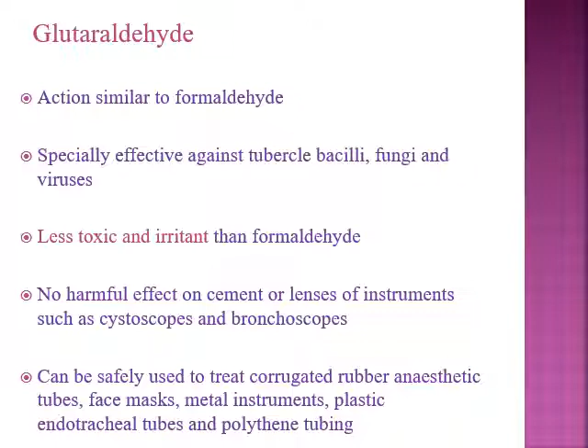Then glutaraldehyde, whose action is similar to formaldehyde. It has a specific effect against tubercle bacilli, fungi, and viruses. It is less toxic and irritant than formaldehyde, with no harmful effect on the cement or lenses of instruments such as cystoscopes or bronchoscopes. It can be safely used to treat corrugated rubber anesthetic tubes, face masks, metal instruments, plastic endotracheal tubes, and polythene tubing. Glutaraldehyde comes in two forms, alkaline and acidic. The alkaline 2% solution requires 10 hours of contact time. It is available as Cidex and 3M germicides. Then the acidic form was introduced in 1969, and its shelf life is longer than that of alkaline glutaraldehyde.